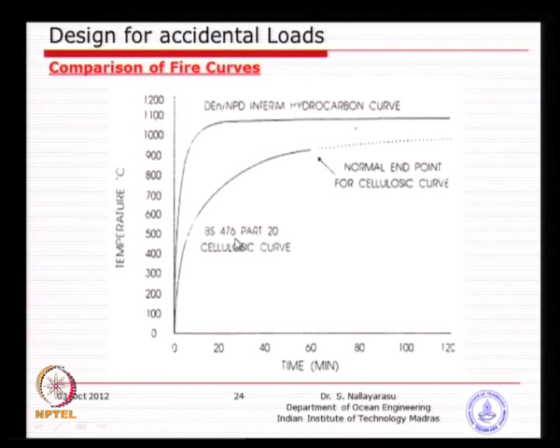So, what are the fire protections? Basically we have active and passive. I think for active, I mentioned the water spray deluge system. I think every building nowadays, especially industrial buildings, is mandated to have a fire deluge system.